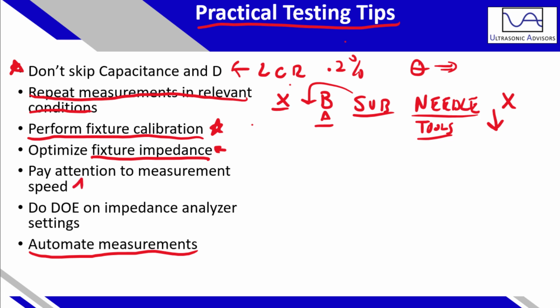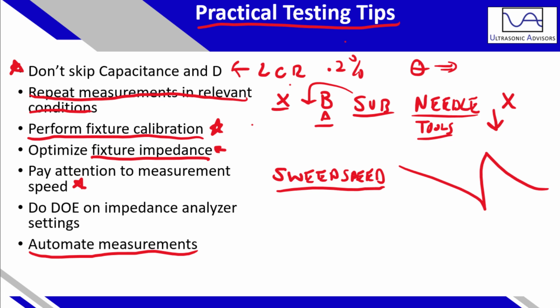Pay attention to measurement speed. And what I mean by measurement speed is sweep speed. So when you perform an impedance analysis, there's a sweep which happens. In my case, I can insert a delay time, or we can specify frequency steps in order to change how fast the measurements are taken. But this has a very large effect on measurements.